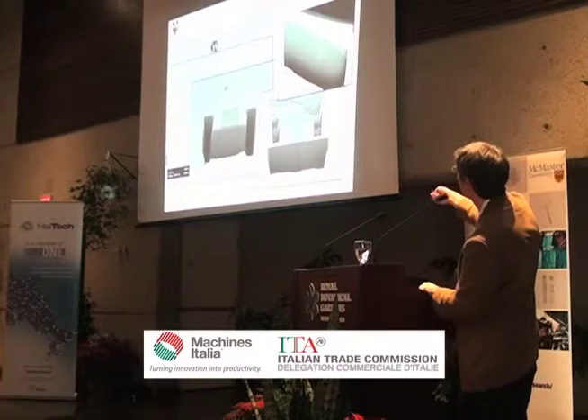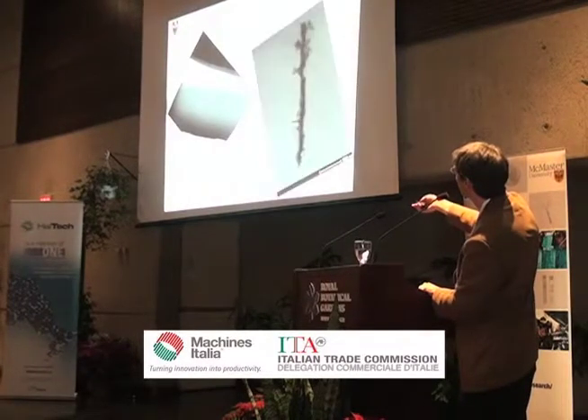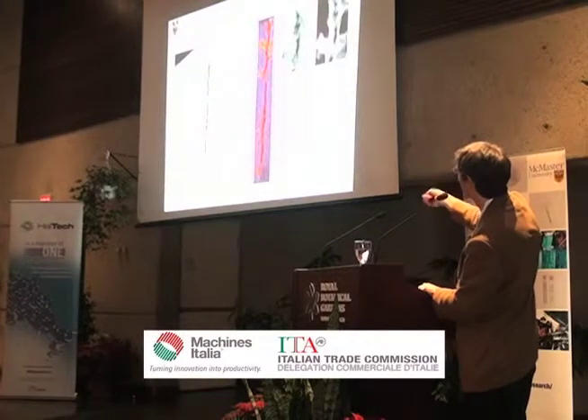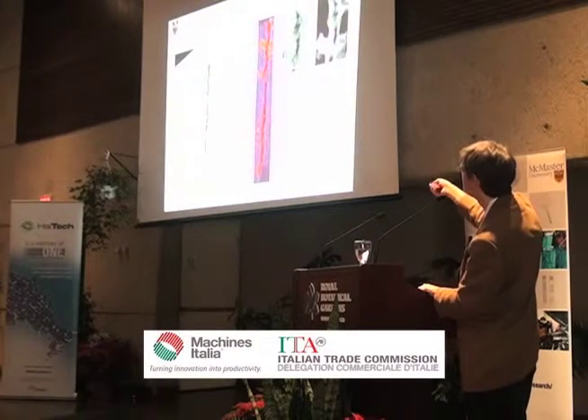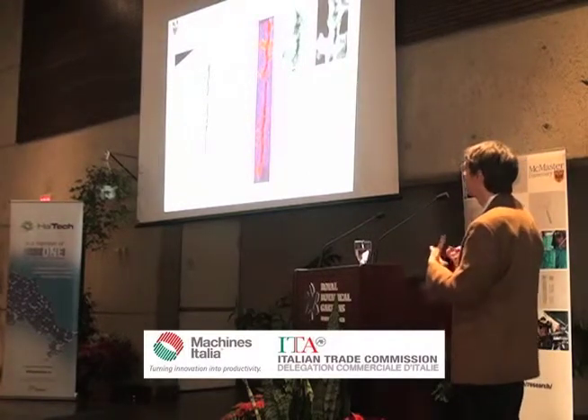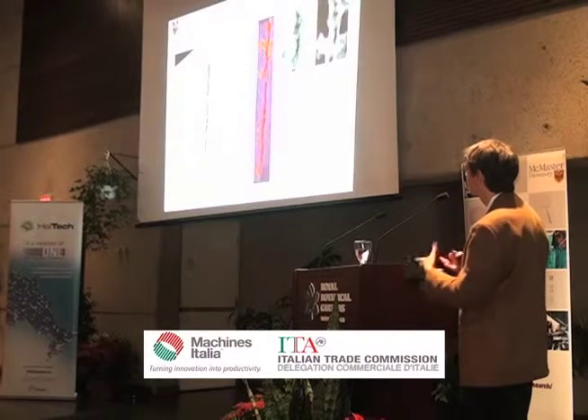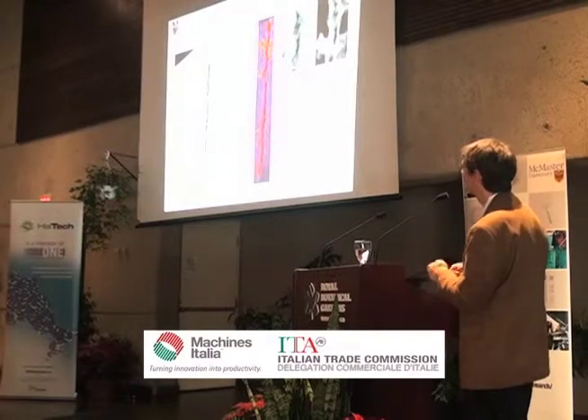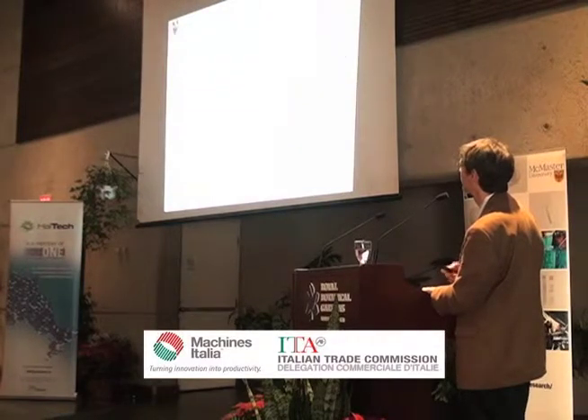So this is the crack tip as it progresses, and we're able to go with a microscope and find out what there is, and do a chemical analysis and find that we have a chromium oxide forming at the crack tip. And that's very useful for the metallurgist engineers, or the engineers in the power plant, to know whether they can actually use these alloys and whether it's safe conditions of operation.